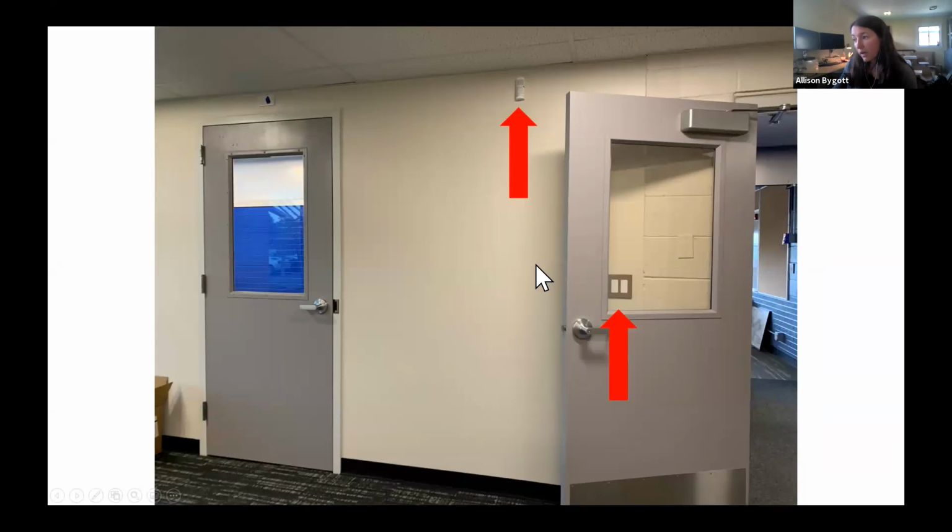This is one of my wireless lighting control projects. I am so sad about this switch. This building was an existing building, but it seems like it would have made more sense to install it over here by the store, because being behind a door is not very helpful. I was told that the likelihood of this door being propped open is low, but these switches are just hard to get to. This is a wireless occupancy sensor.